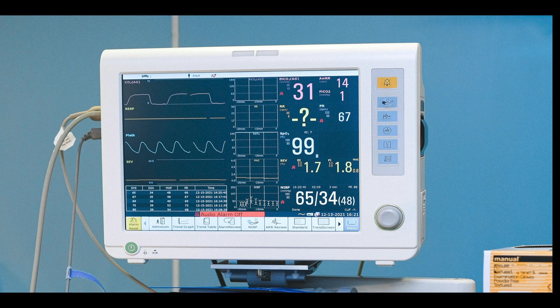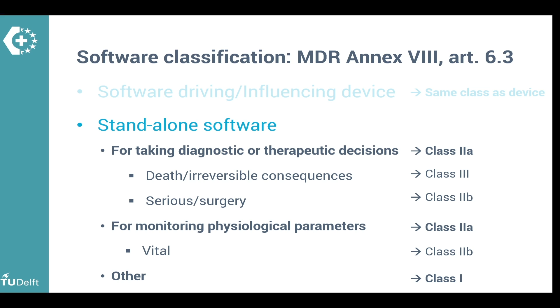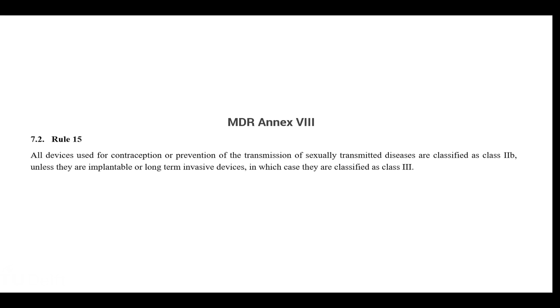That all seems quite straightforward, but do mind that if the software is a medical device, you must also check all the other classification rules for medical devices. And although many do not apply to software, there are some that do. For example, Rule 15 in Annex 8 states that any device used for contraception is Class 2B. Therefore, if some software would calculate based on someone's menstrual cycle when to have intercourse with a minimal risk of getting pregnant, that software would also be Class 2B. But of course, this would be a very unreliable form of contraception. Finally, if you need more support in classifying software, also check this EU guidance document.